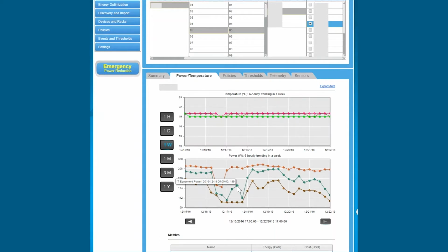But basically, the server itself is actually monitoring this data every millisecond. So every data point Intel DCM has is actually built from a large amount of data collected from the server. And this is why we're presenting here 3 values for every measured point that we have in the environment. The first value is the highest power consumption that this server measured within these couple of minutes, the average power consumption, and the lowest. And this way you can get a full picture of the data that the server is collecting every millisecond. So this is the trending analysis for a single point of data.